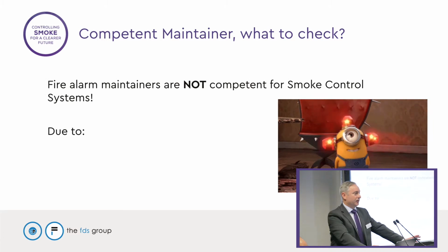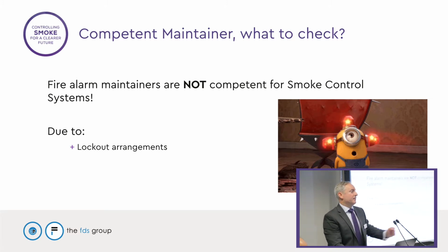Well, we don't really want fire alarm maintainers because there's a number of reasons. They don't understand the arrangements for smoke control lockout. So this is a concept that a fire alarm company just wouldn't, unless they're familiar with smoke control, wouldn't understand. Yeah, they'll go around and test all your heads and check that the panel makes an alarming noise, but they're probably not familiar that the lockout arrangements only allow for one floor to go into fire condition, and all the other floors should lock out and close because the design is specified to only provide ventilation on one floor. A fire alarm company expect multiple fires on multiple floors, and the system should alarm in every place.